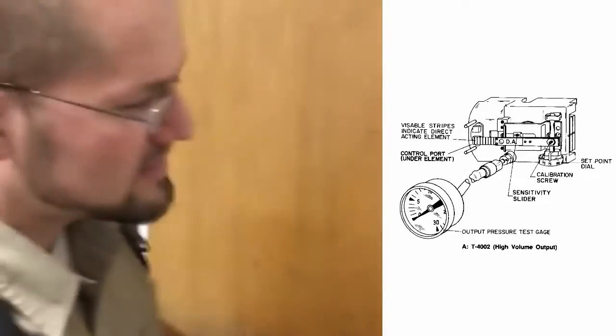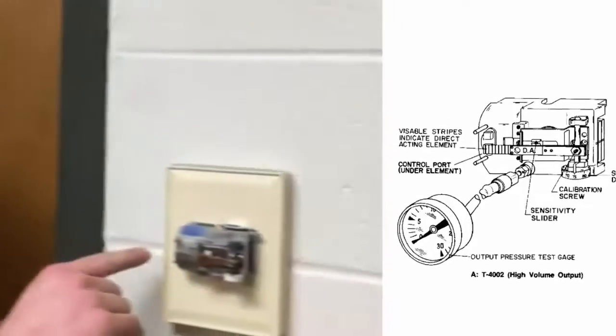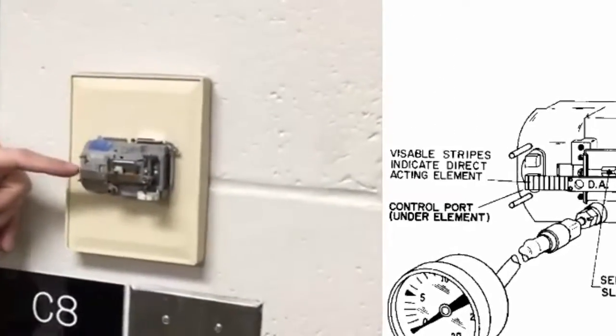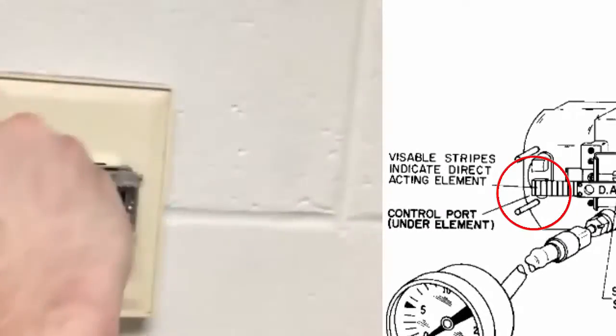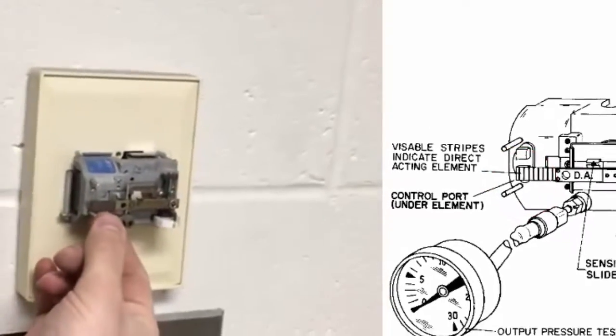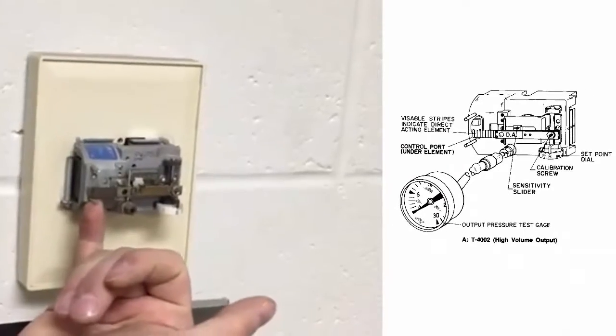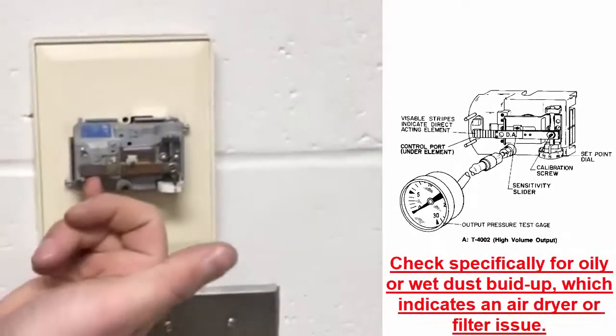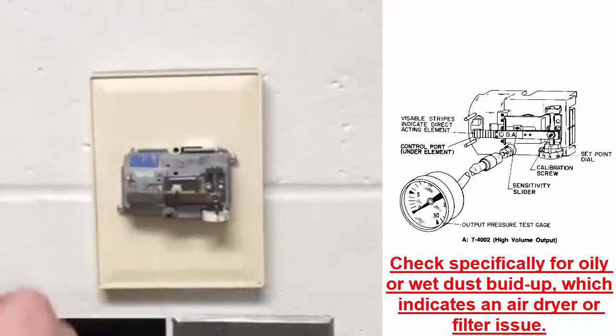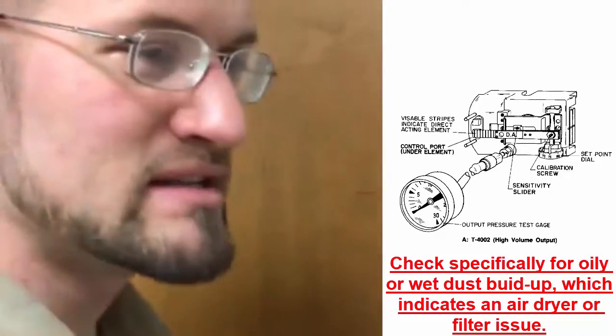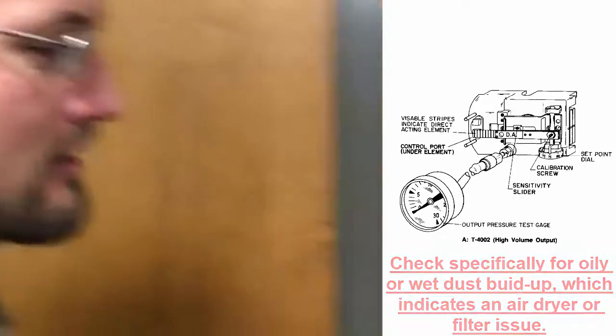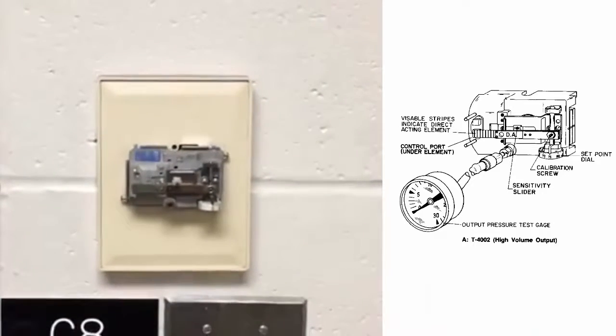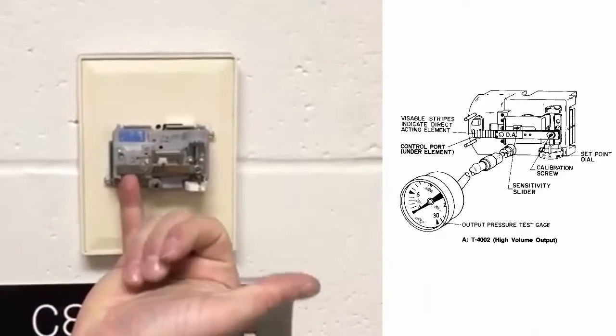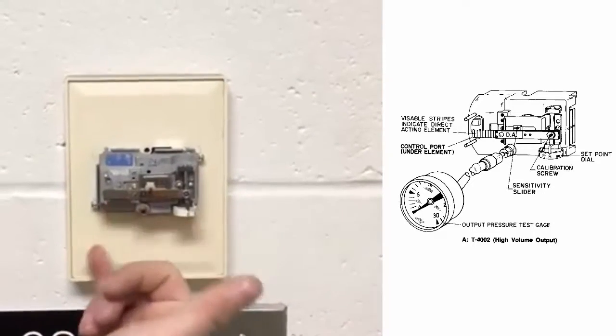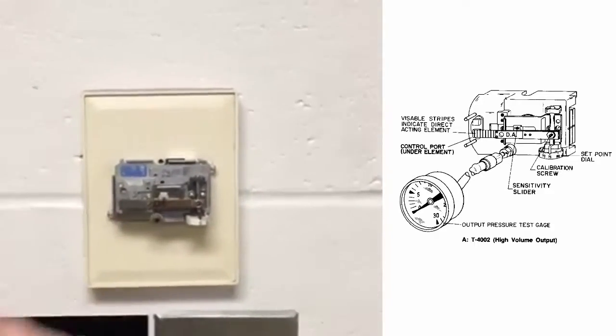Alright, so on these Johnson stats, the first thing you want to really check on them is whether this exhaust port is covered in dust. If you get a lot of dust in here, it'll keep this from sealing properly. If you get a leak here at all, it's usually in most cases going to result in loss of pressure and heating. So if you've got a space that's overheating, start by checking there. The easiest thing to do to clean it is take a pipe cleaner or something, just drag it behind there lightly and clean the dust off of it.